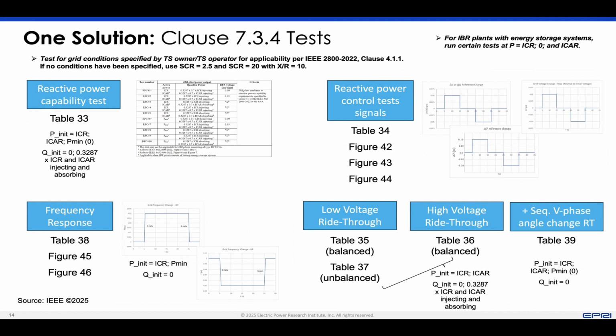2800.2 proposes specific tests for reactive power capability, reactive power response, and voltage response, frequency response, low voltage ride-through, high voltage ride-through, or even transient overvoltage, and positive sequence voltage phase angle change ride-through. So the standard actually says that these tests shall be run at a strong and also at a weak grid condition. But not always does the transmission system planner provide specific numbers for what that actually means.